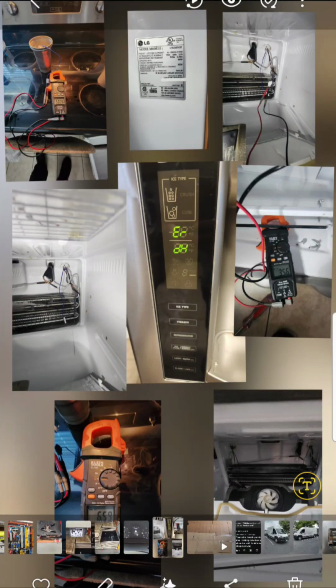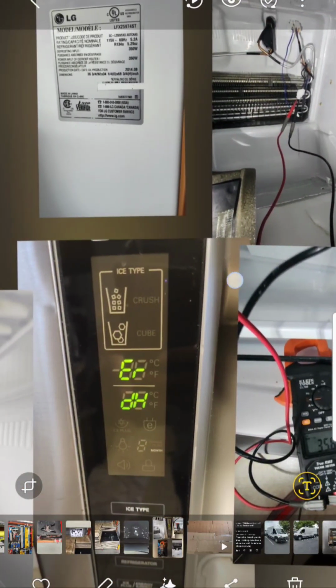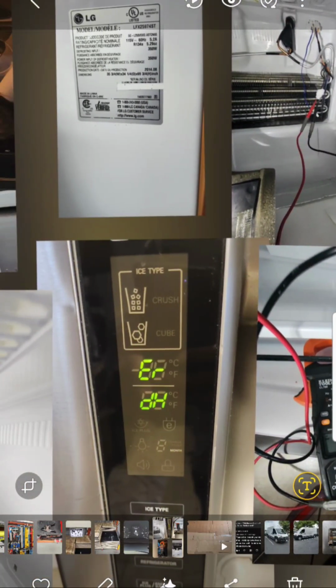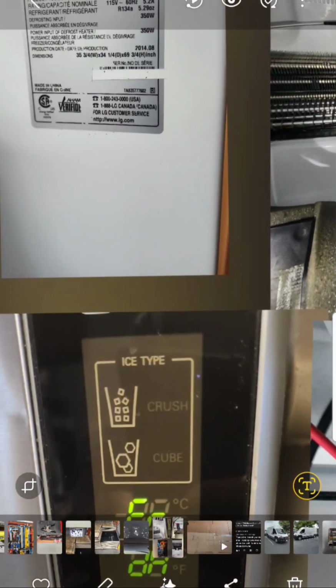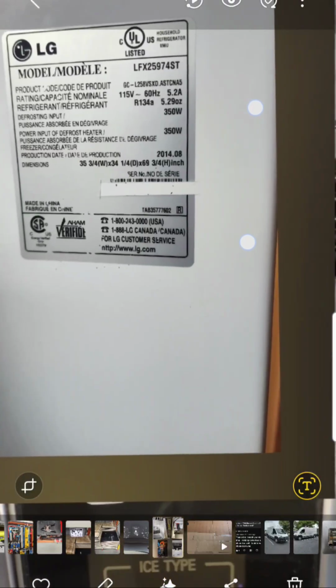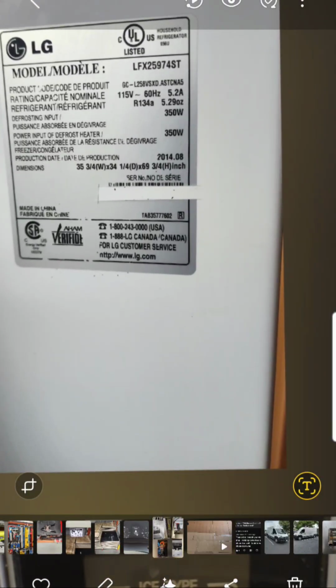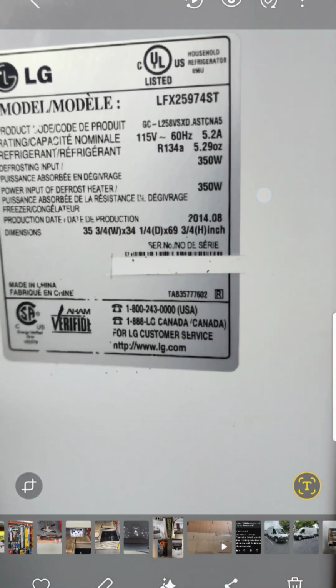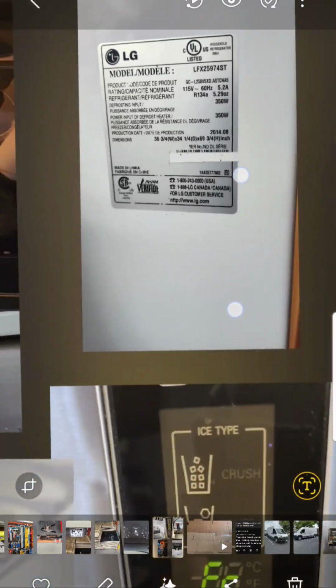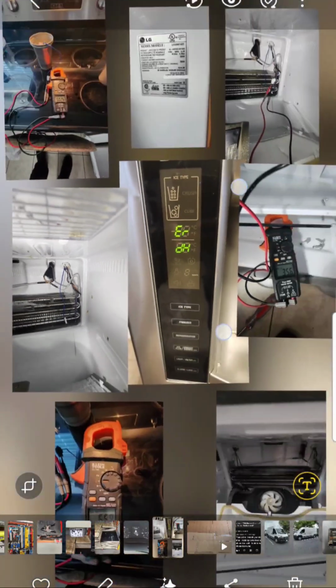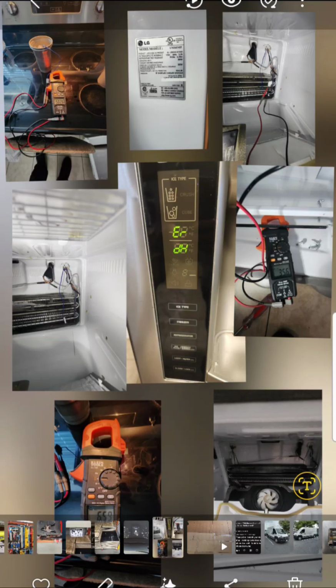So those are some steps you could take to troubleshoot something like that if you ever run into an issue with an error code on a refrigerator. And as you can see here, you can see the information. It's an LG unit, and the model number is right up there on the top of the data plate. So if you ever run into that, be sure to check those areas first.